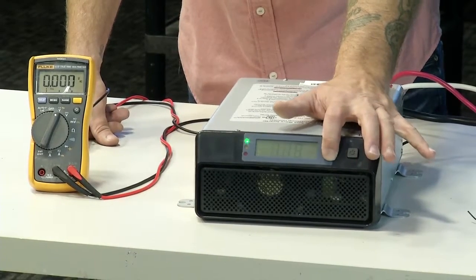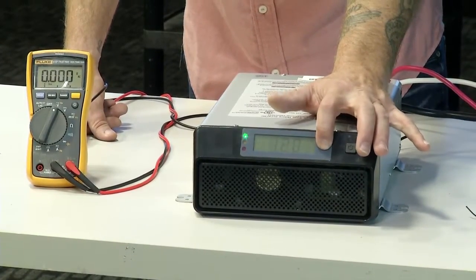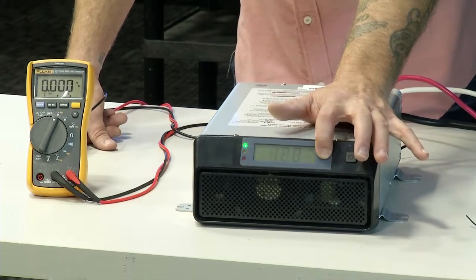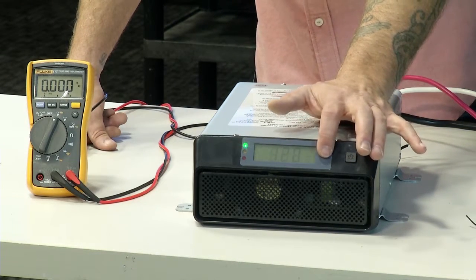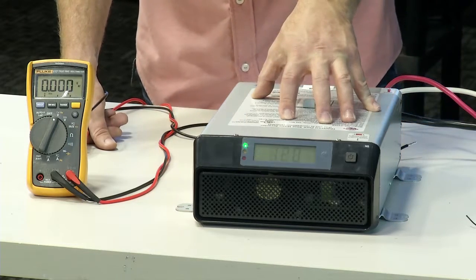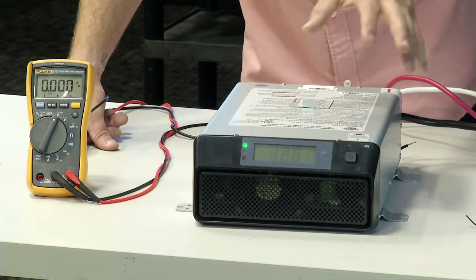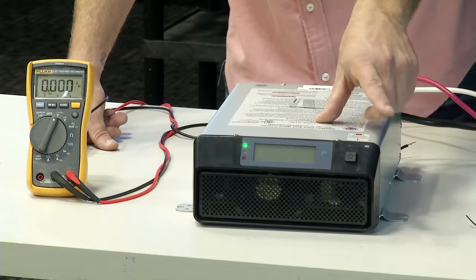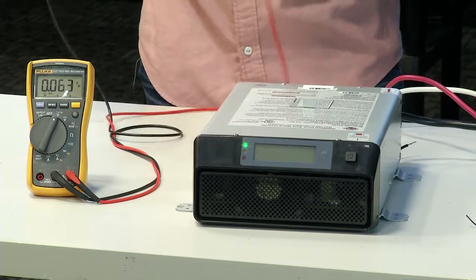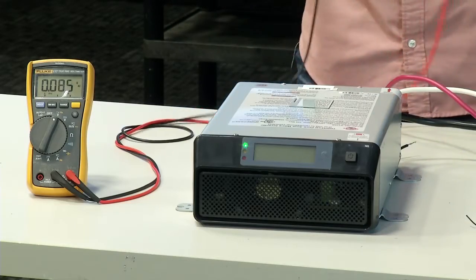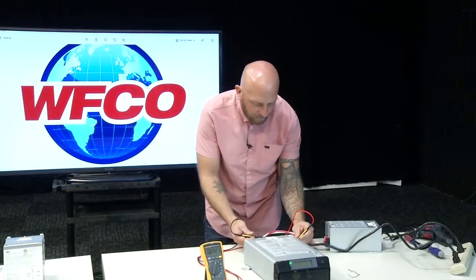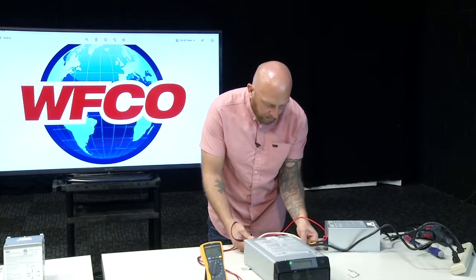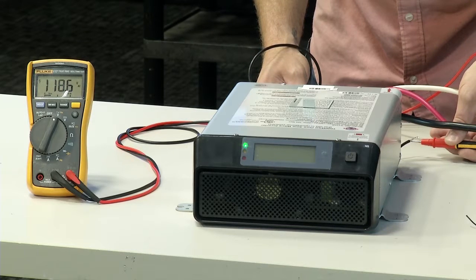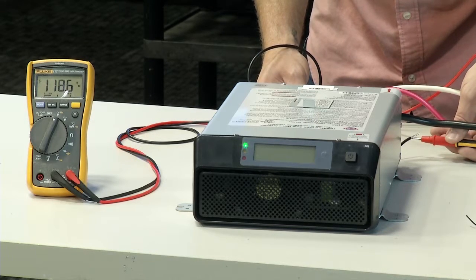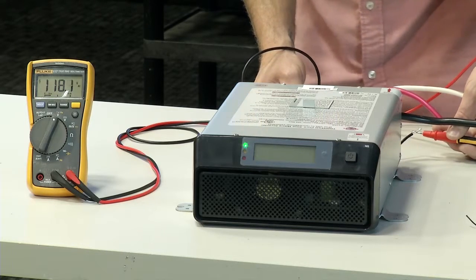This little button that we just used a second ago will not work on shore power. So when that light's green, all it's going to tell you is what it's passing through, because the inverter's not technically doing anything other than passing through the voltage. Even if you turn this button off and you're on pass-through, that green light's on, you're still going to have hot voltage coming out the back of this inverter. So if you measure between your black and white wire again out the back, which is your output, we're getting 118 volts. So just because your button's not in the on position, if you have a green light on, these wires are still hot.